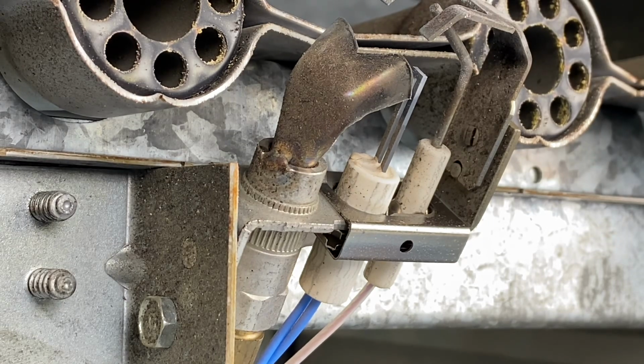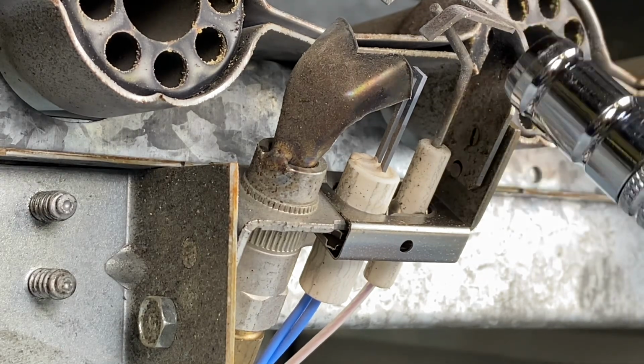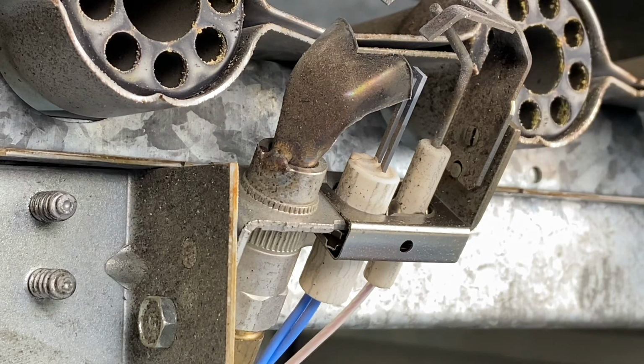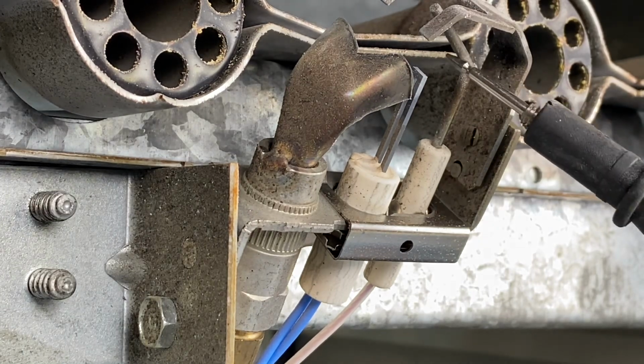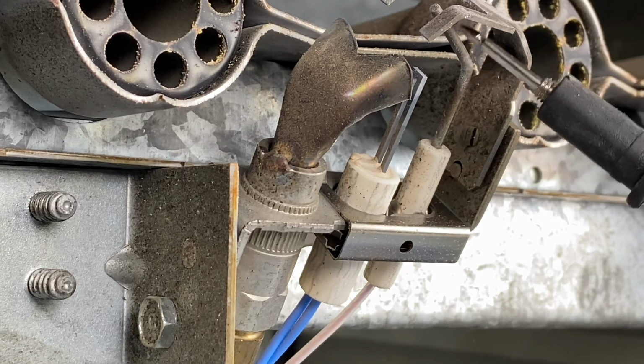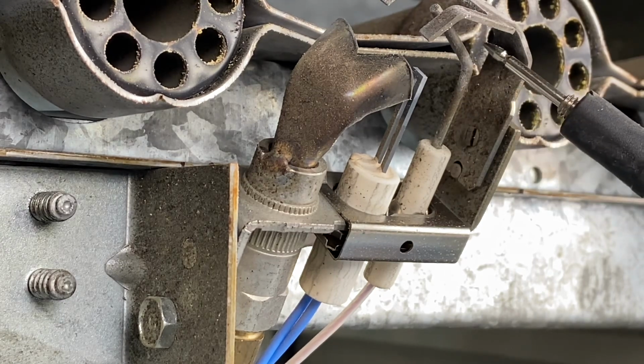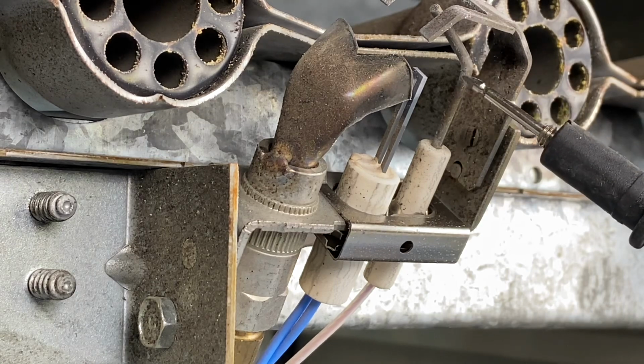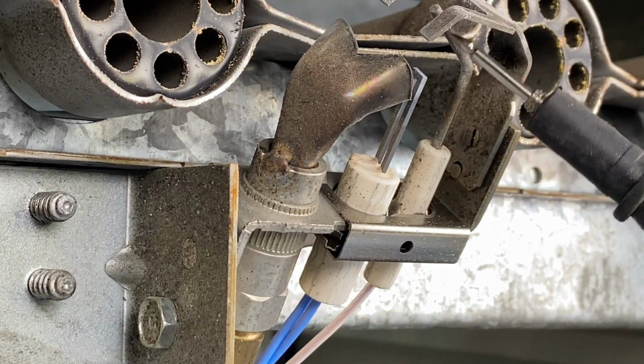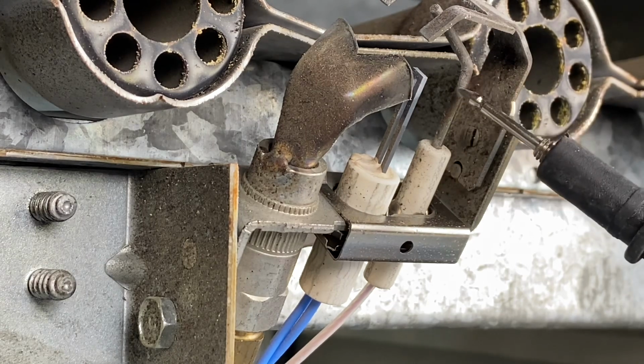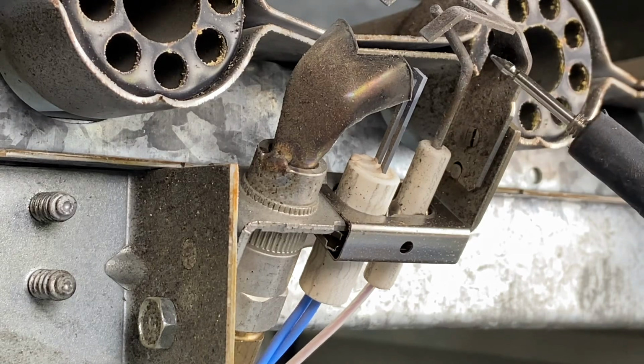So in the past, we would try to clean these flame sensors. We had to be very, very careful cleaning that flame sensor that you didn't even touch that hot surface igniter because it would break all the time. So it was very difficult cleaning these flame rods. I always hated it because you had to clean the flame rod, but you also had to stay away from this. So this is the flame rod, and you can see there's this discoloration on there. So this is definitely getting dirty, and we would have to clean this up, and we'd have to use something like a type of Brillo pad, but we'd never use sandpaper because sandpaper would gouge this, and the sand on the sandpaper would leave a coating which would cause this to have a type of glass coating and not work very well.